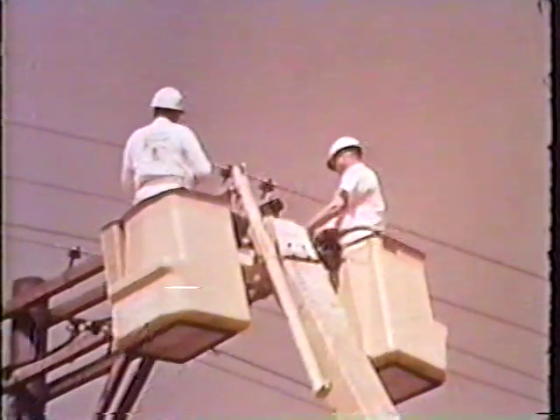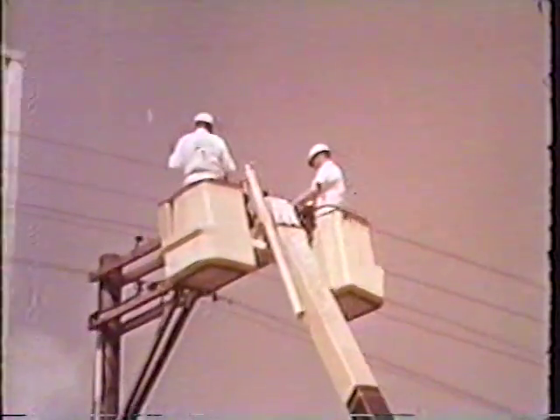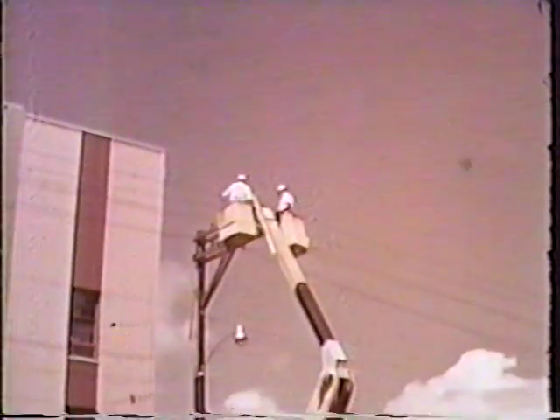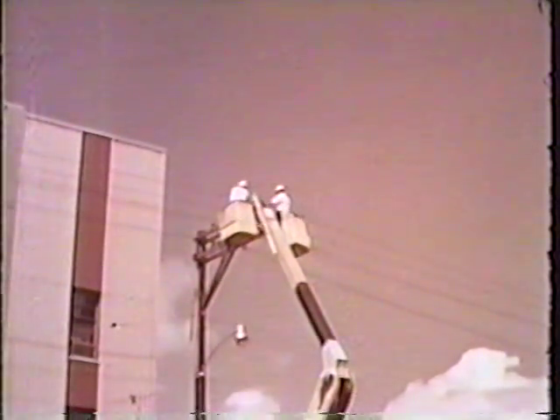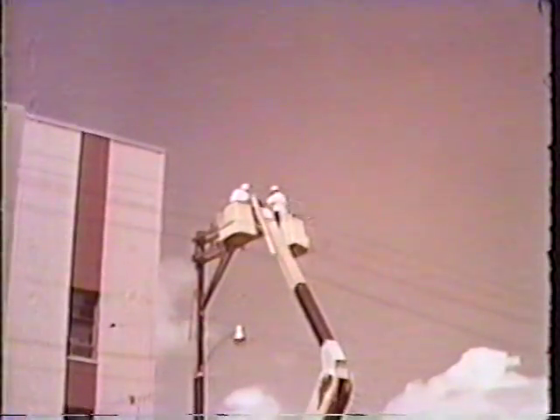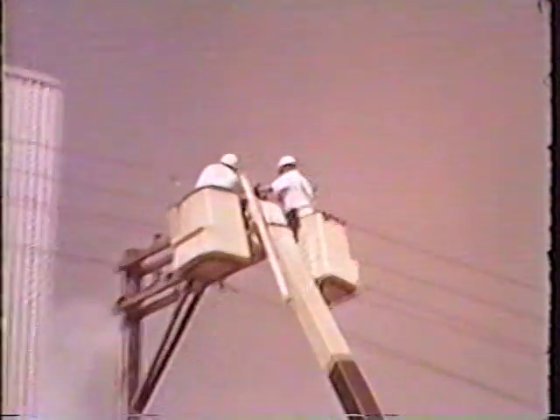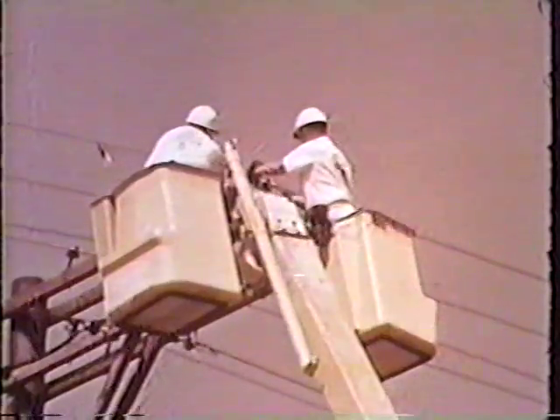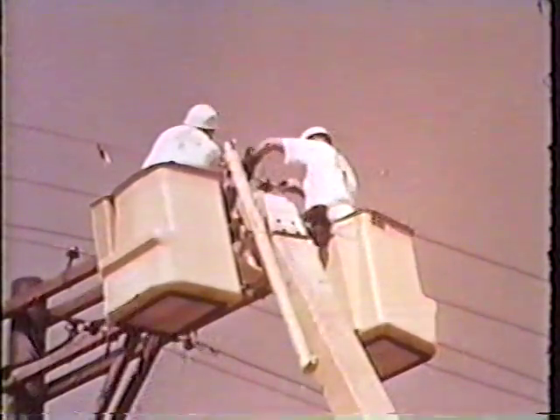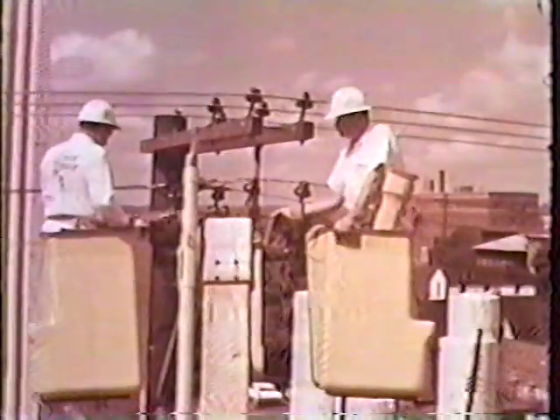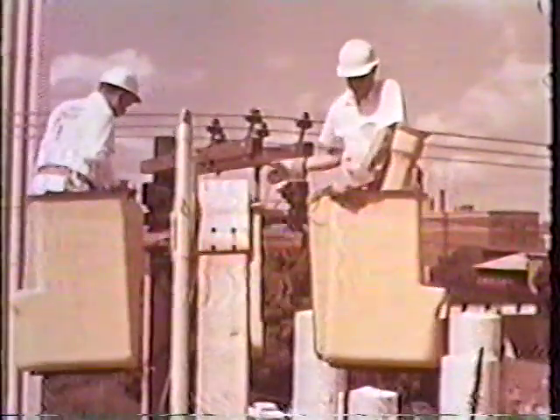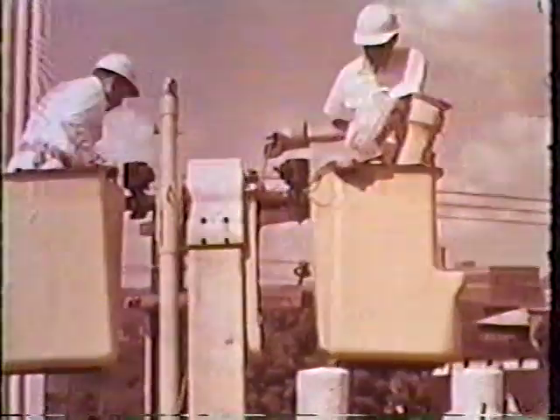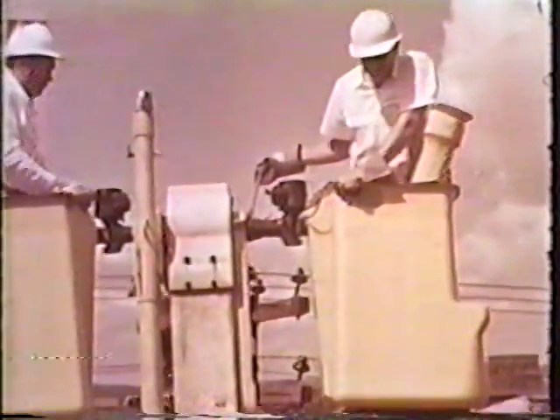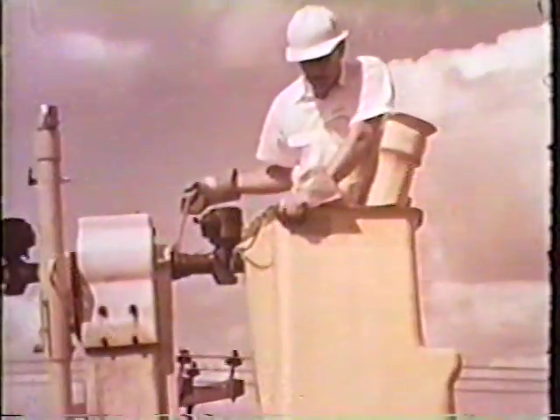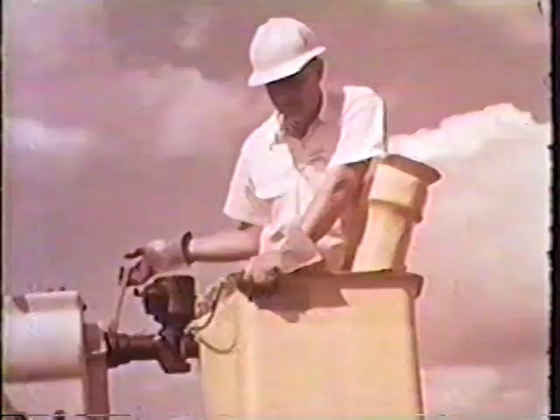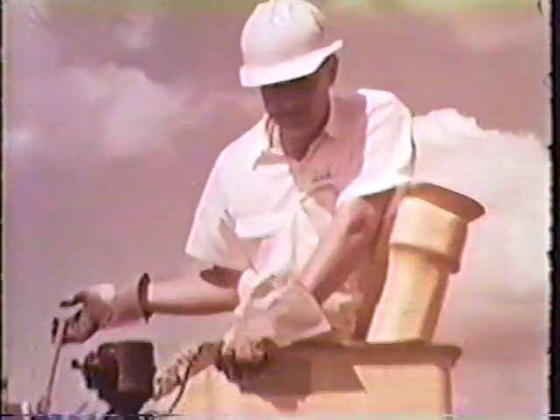Using barriers on the double arm, the bare-hand crew is replacing a broken tie wire on the end of a 12.5 kV alley arm in another congested downtown area. The job quickly completed, the crew pulls away, carrying the largest cover-up material in the personnel buckets with them. Tools and smaller equipment are in the small tool trays attached to the far side of the buckets.